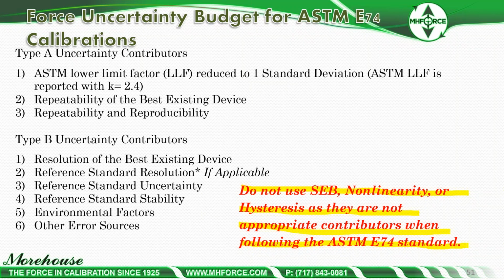Just wrote a paper for Cal Lab on this topic, millivolt per volt calibration curve versus 2-point span, and there was like a 2,000% difference. I mean, we're talking small numbers, so be cognizant when I say 2,000%. You're talking 0.2 to a 0.01 type scenario, but it still can be a big difference on the load cell.